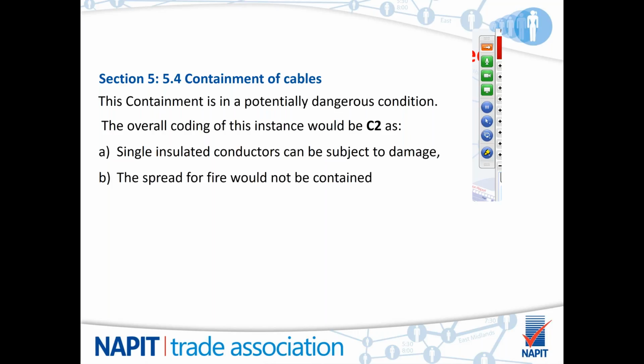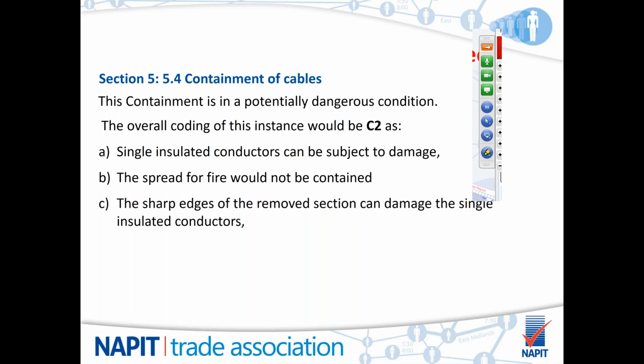Without the lid, we've got a possible spread of fire. If anything happens, the ingress of oxygen would increase the fire risks. And of course, the removal of the section has only left sharp edges that conductors could come into contact with.